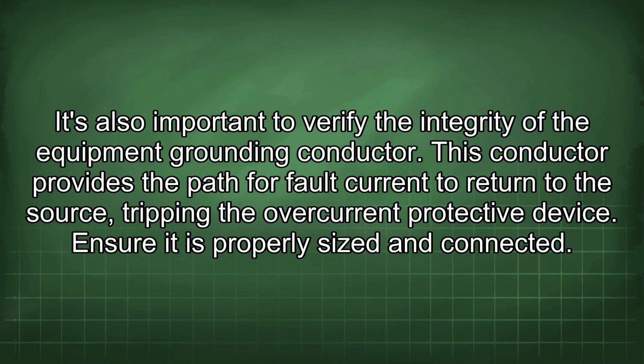It's also important to verify the integrity of the equipment grounding conductor. This conductor provides the path for fault current to return to the source, tripping the overcurrent protective device. Ensure it is properly sized and connected.